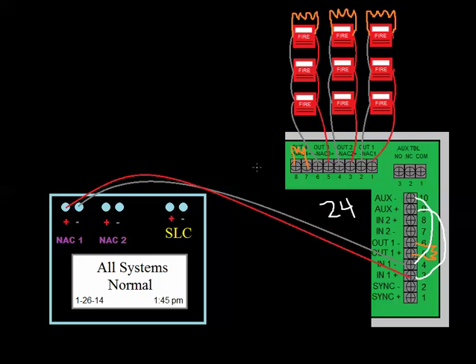If you're using Wheelock sync code, you have to use all Wheelock devices. You can't have even one System Sensor or Gentex device on that circuit that you're trying to sync.